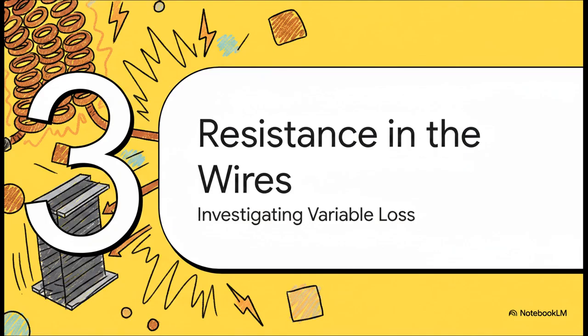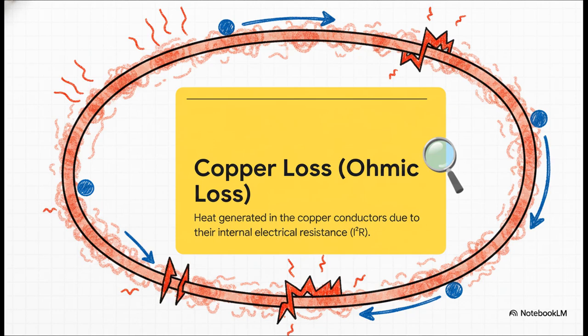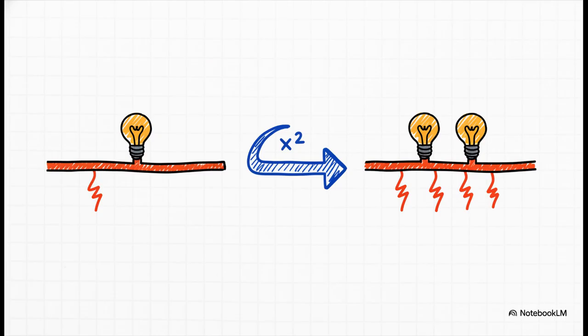Now, let's turn our attention to the other side of the equation, the variable losses. These are the ones that happen in the copper windings that are wrapped around that core. This is the biggest variable loss, and it's usually called copper loss. It's really just simple physics. Every wire has some amount of electrical resistance. So as current flows through those copper windings to power our homes and businesses, that resistance basically creates friction for the electrons, and that generates heat. The more current that flows, the more heat you get. But here's the crucial part. This relationship is not a straight line. The loss actually increases with the square of the current. What that means is, if you double the load on a transformer, you don't just get double the copper loss, you actually get 4 times the loss. This is a massive deal for the engineers who are designing our power grids.